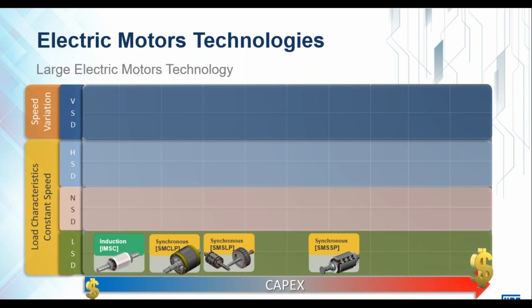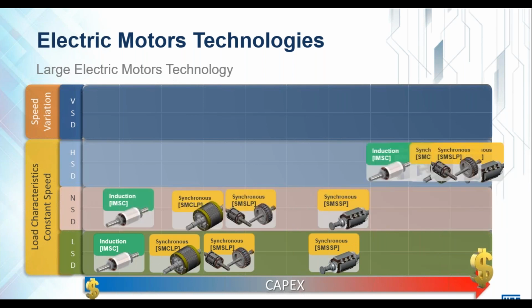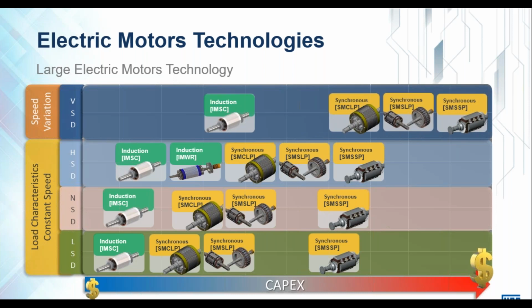Okay, so just to tie this all up, we're doing a comparison here of the load conditions versus capex. So what are the most expensive machines to install? Quite obviously, in light starting duty application, a standard induction motor would be the cheapest installation from a capex point of view. And then you can see the synchronous machines get more expensive, from a cylindrical synchronous machine up to a salient laminated pole, and then a solid laminated pole design.